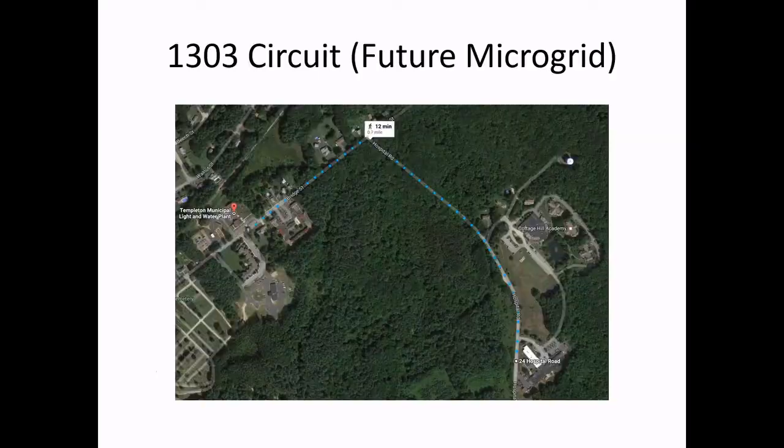Regarding resiliency and future microgrid potential: the 1303 circuit, one of four circuits coming out of the Templeton substation, serves quite a few critical care facilities — a residential treatment facility, a nursing home, and a senior housing facility, all within less than a mile of that circuit. The decision was made to install the battery on that 1303 circuit so that in the future, with additional switching, it would be relatively easy to island it and provide up to 24 to 36 hours of backup power to these critical pieces of infrastructure during an ice storm or other natural disaster.